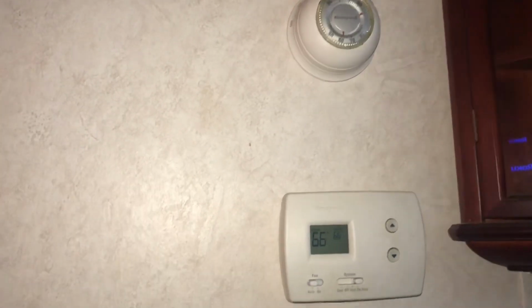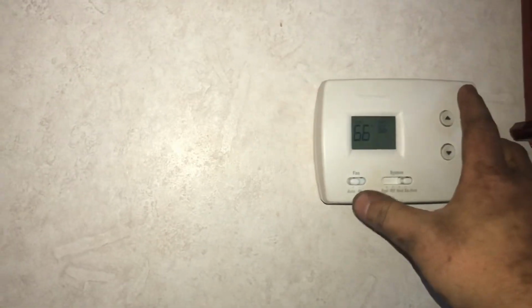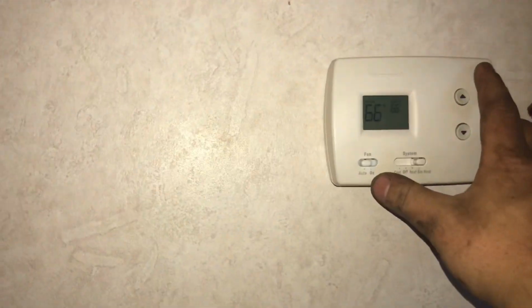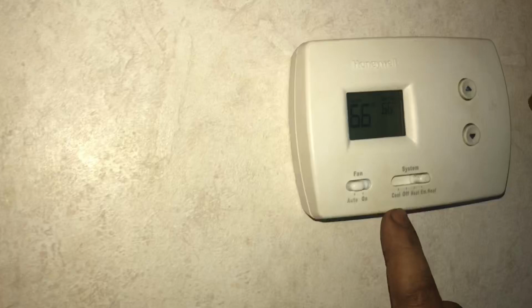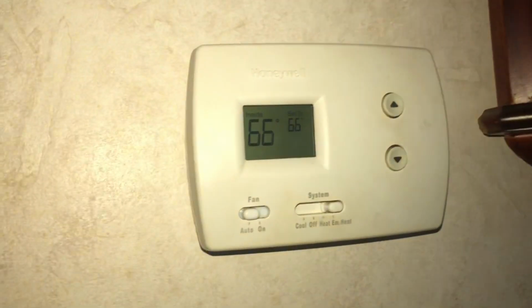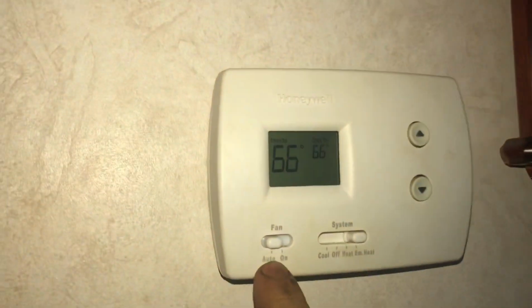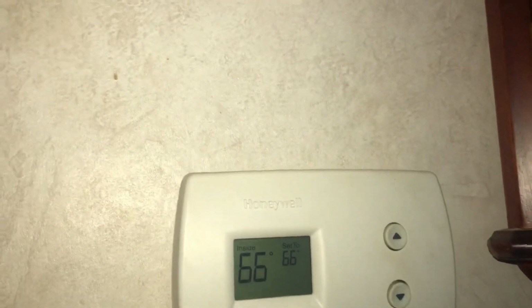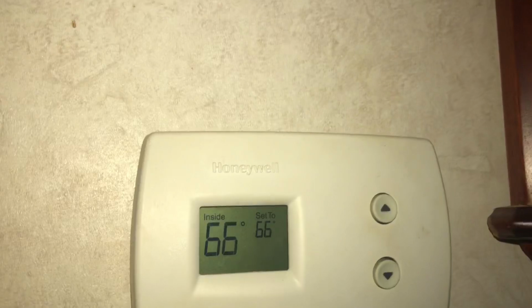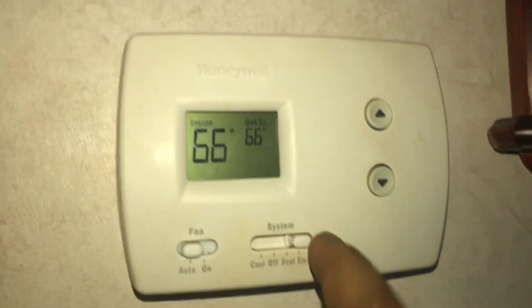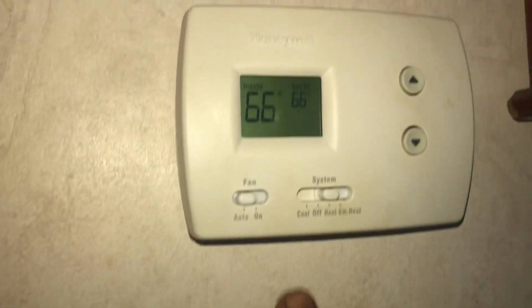Okay, and the way I've got my thermostat set up is I have two thermostats. I have the basic thermostat that comes with the furnace, and everything works on it the way it should. What I've done is run a wire into this other thermostat - you have to find where the fan switch is, then run one wire so this essentially becomes a switch for that fan switch. So this unit will stay on heat or emergency heat depending on what temperature is outside.